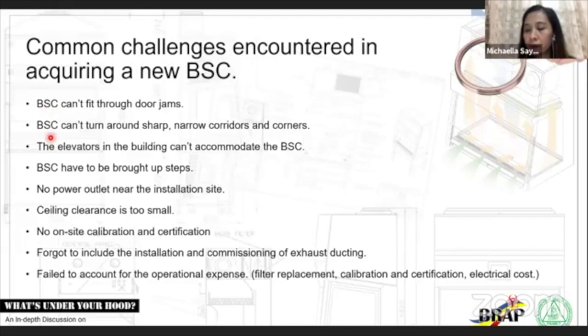Now, the second one is elevators, or second floor or higher floor installations. You might check again the weight of your biosafety cabinet and talk to your engineer and ask them if your elevator can actually carry your biosafety cabinet up to the next floors. Imagine buying 700,000 equipment and not being able to use it just because you cannot bring it up the stairs or up your elevator, right? That would be very frustrating.